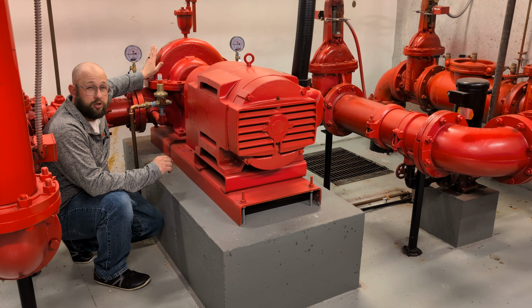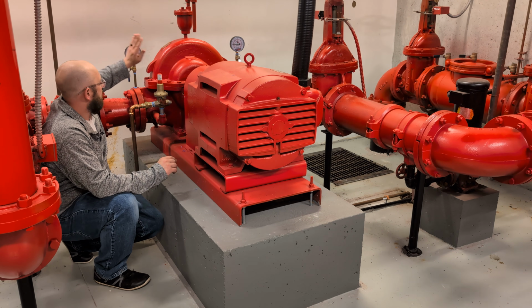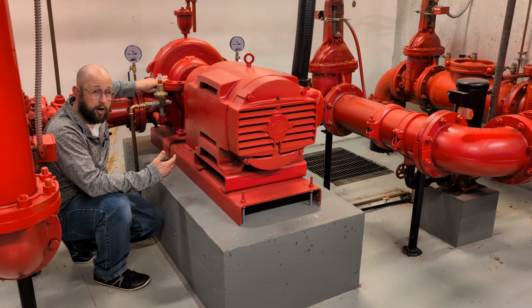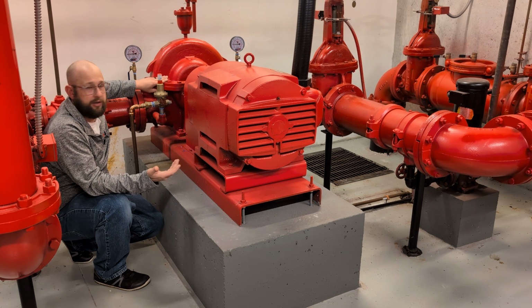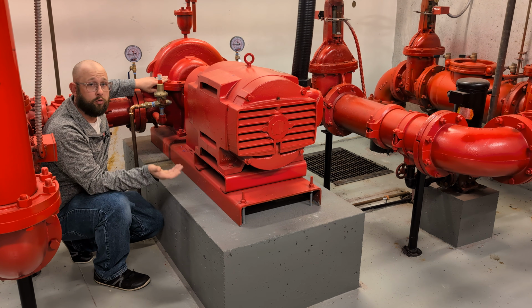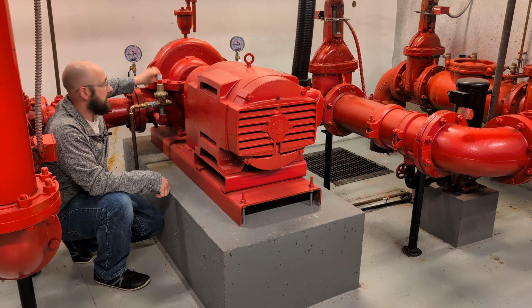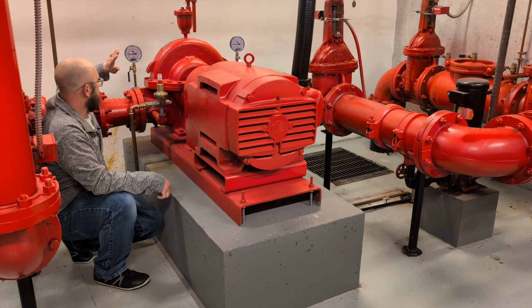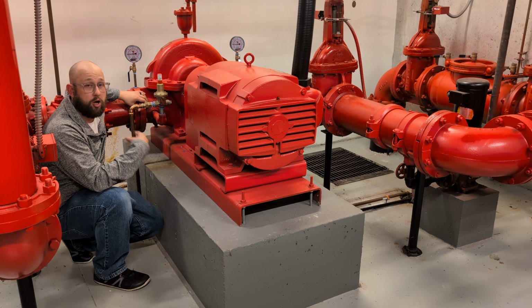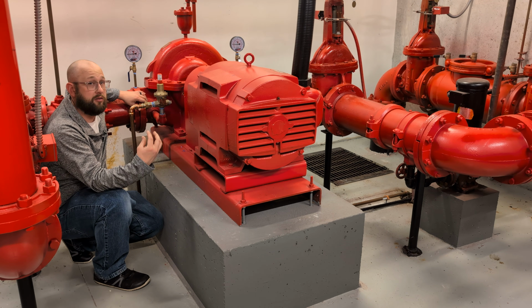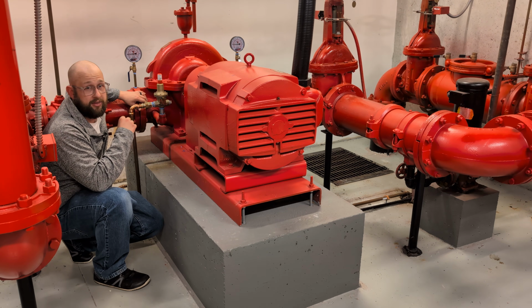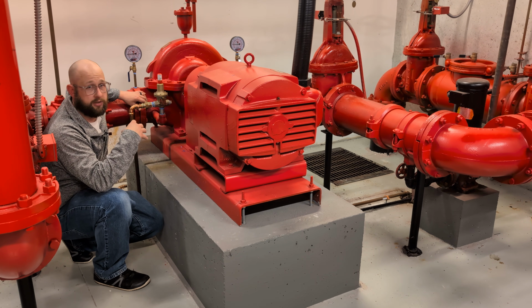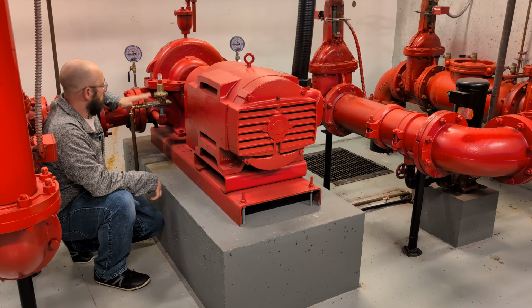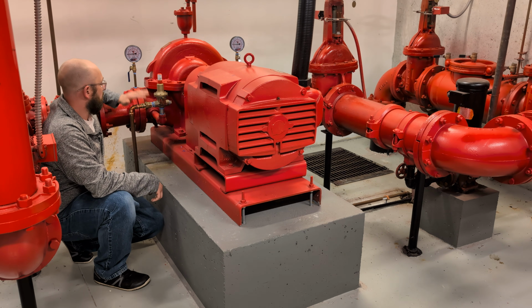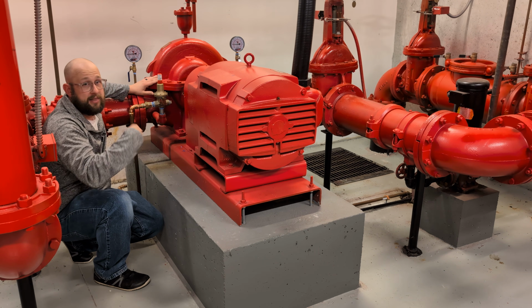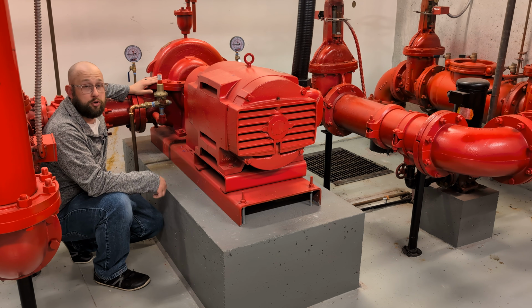There's a couple conditions in which you might not need a circulation relief valve. The first one being if we have a vertical turbine pump and the pump's actually down in the water. We don't need a circulation relief valve because the pump's constantly being cooled by that water. Or if we have a diesel-driven fire pump and we're coming off of the discharge piping going through the cooling system for that diesel pump, we don't need a circulation relief valve in that case because that cooling water coming off of it is causing the cooling of the pump. But for the most part, we are required to have that circulation relief valve here, and it is for cooling the pump casing while we're running in that churn condition, which happens quite often when we're doing our churn pump testing.